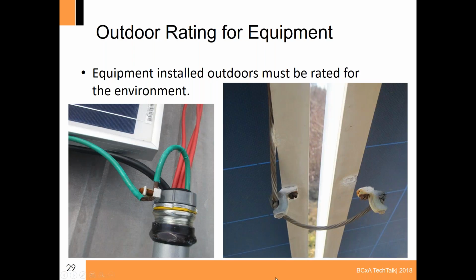And lastly, outdoor rating for equipment. Another common issue is installing equipment that has not been rated for the environment. So this can be verified by specification sheets on the front end, but also a visual inspection after the equipment has been exposed to these conditions. So I'd say personally the most common misused component on an outdoor rooftop solar installation is going to be this fitting here. This is called a bonding bushing, where basically it allows us to attach a ground wire to a metal conduit. 99% of the bonding bushings out there are not listed for outdoor use. And this, I guarantee, is probably after 1 or 2 months.